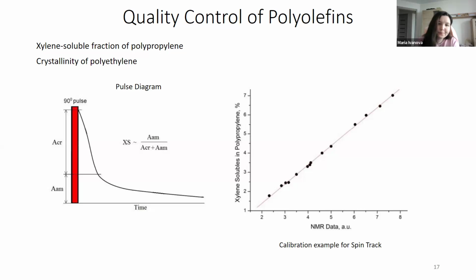On the right side of the slide, the calibration between xylene solubles in polypropylene from reference values, known from wet chemistry, versus the NMR data. So the dependence is clearly linear, and the analysis in general is simple and fast and doesn't require any solvents or long conditioning.